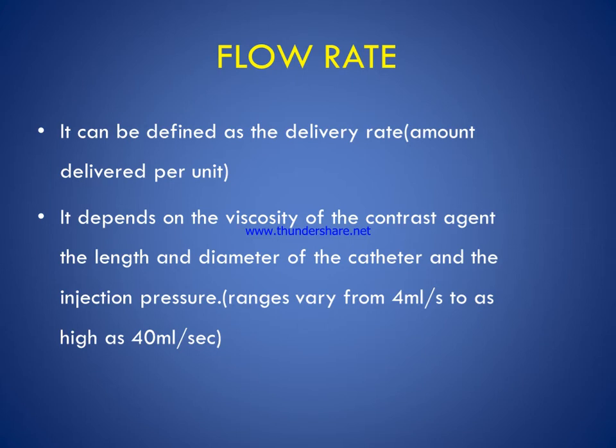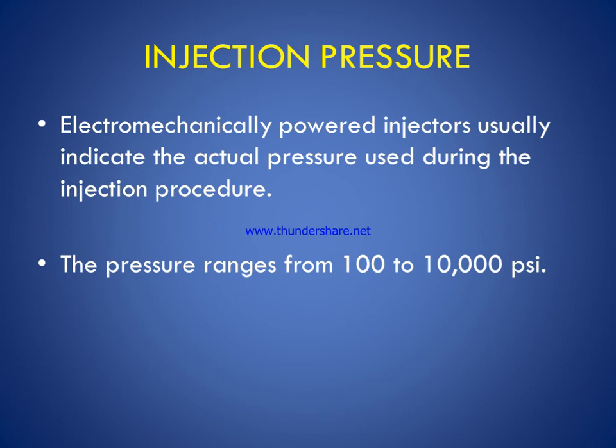Flow rate is defined as the delivery rate or amount delivered per unit time. It depends on the viscosity of the contrast agent, the length and diameter of the catheter, and injection pressure. It may vary from 4 ml to 40 ml per second. Injection pressure in an electromechanically powered injector indicates the actual pressure used during the injection procedure, ranging from 100 to 10,000 psi.